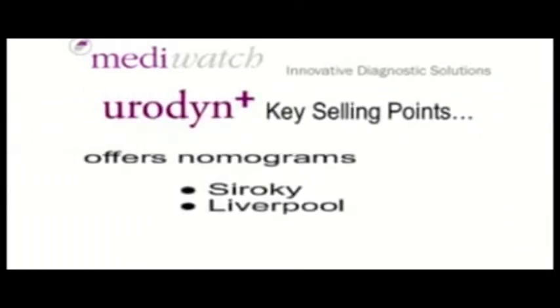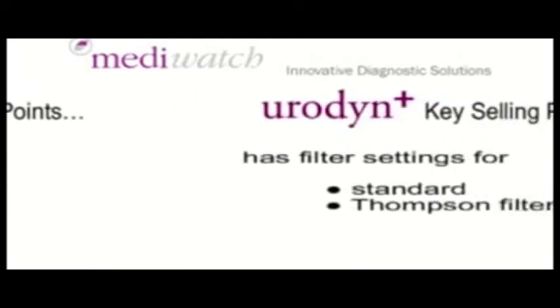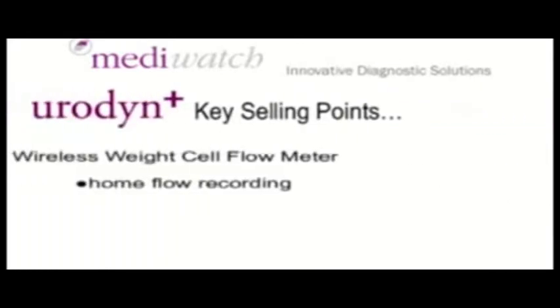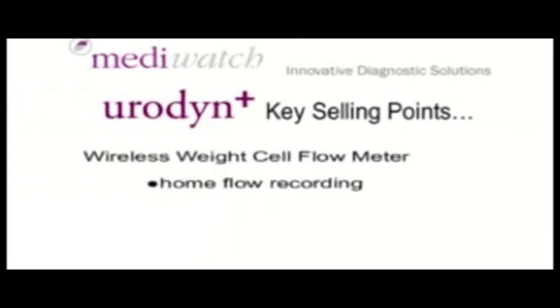Urodyne Plus offers nomograms — Siroky and Liverpool. Urodyne Plus has filter settings for standard and Thompson filters, and the wireless weight cell flow meter can be used for home flow recording.